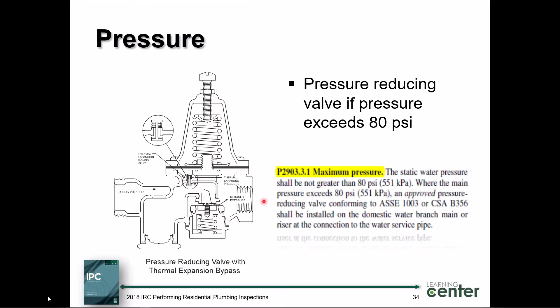This is our guarantee. Because you know what? We live in the United States. We have standards to follow and codes to follow. That enables us to design and build a safe plumbing system. Here's my supply pressure coming in, 100 PSI. I could take this screw, either depress or uncompress the spring tension here, and it will regulate the pressure coming out of this particular valve. So I can go from 100 and set this thing to 60 PSI, 50 PSI, cannot be greater than 80 PSI.